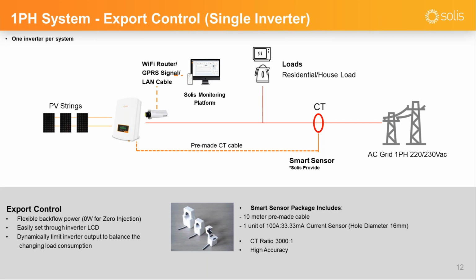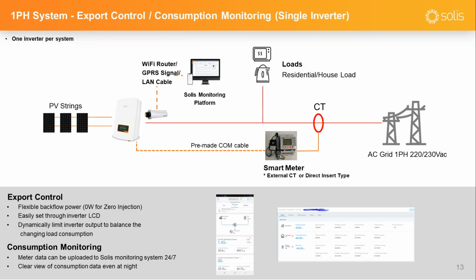And other than the smart sensor solution, we can also provide the smart meter solution. So if you order the inverter with a meter port, then it can connect to the smart meter with a pre-made COM cable provided by Solis. And also the smart meter has two types. One is the external CT type and another is a direct insert type that we'll talk about in the next slide. And with this smart meter, other than the export power control function, which is pretty much the same as connecting a smart sensor, another function is that we can do the consumption monitoring. So with this smart meter connected to the inverter, and then you do some settings on the inverter, then we can achieve the power flow monitoring.